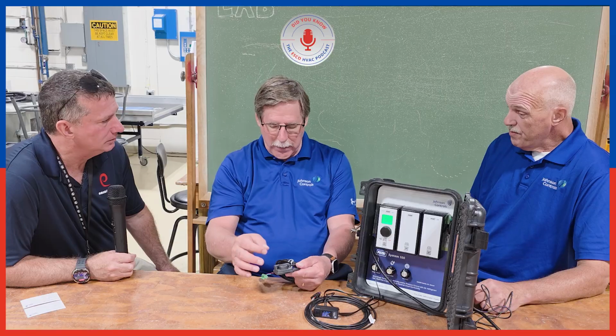The other thing Bill talked about, to tee off that, is now we've got 5 different sensors, one calibrated for each A2L refrigerant, 2 on the HVAC side, 3 on the commercial refrigeration side. In the future, you'll find there'll be a dual refrigerant sensor on the HVAC side, so we'll have to take some compromises in terms of what the LFL level is, what the refrigerant is, and what the trip point is programmed for.